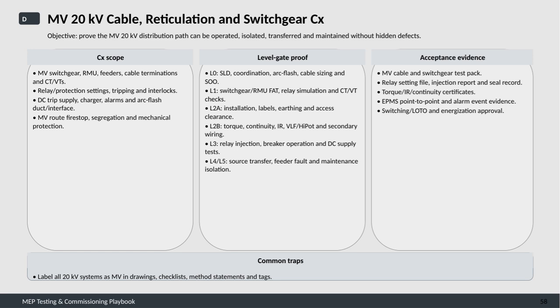Level 2B focuses on torque settings, electrical continuity, insulation resistance, and advanced cable testing like VLF or HiPOT, plus secondary wiring verifications. Level 3 covers relay injection tests, breaker operations, and DC supply tests. Finally, Levels 4 and 5 validate source transfer procedures, feeder fault handling, and maintenance isolation protocols.